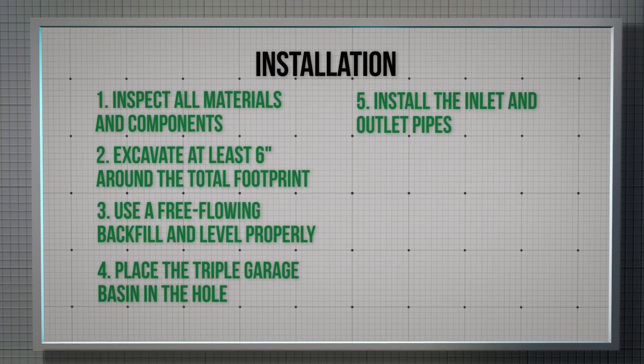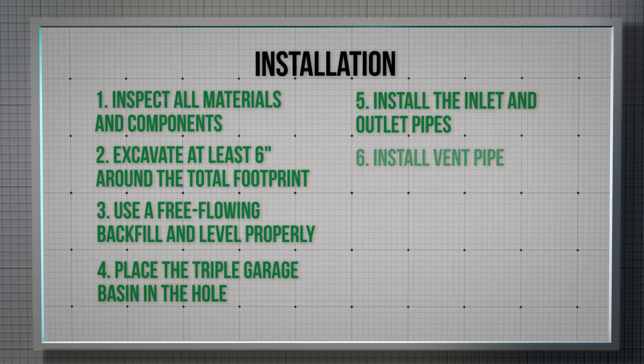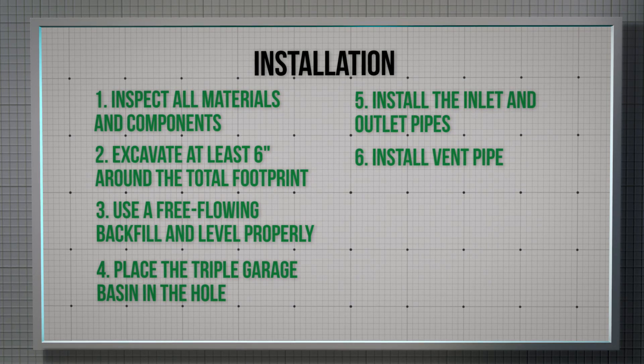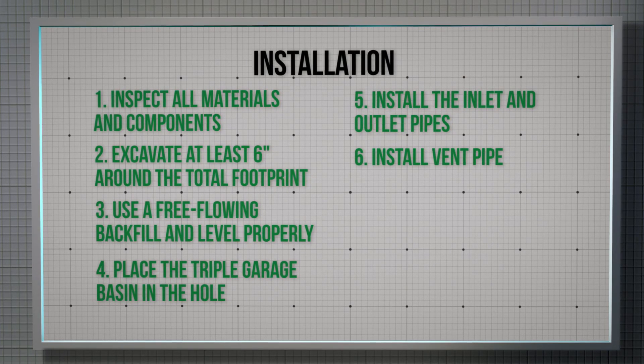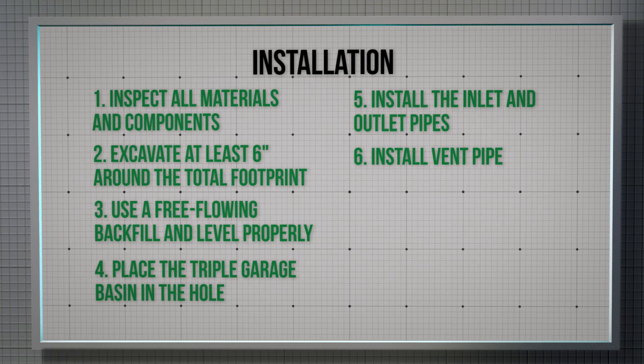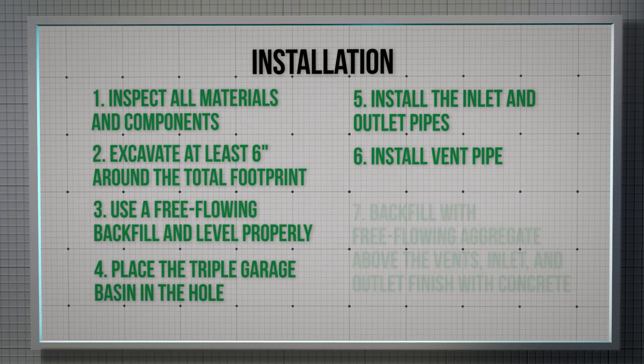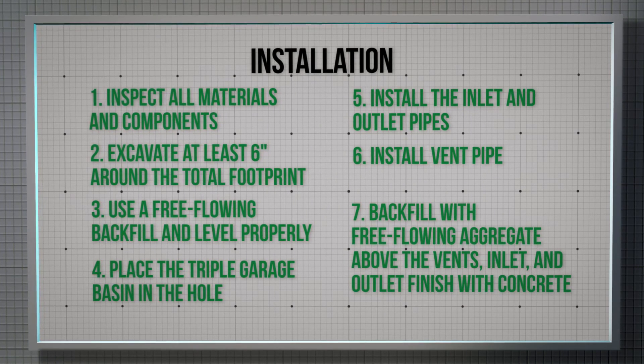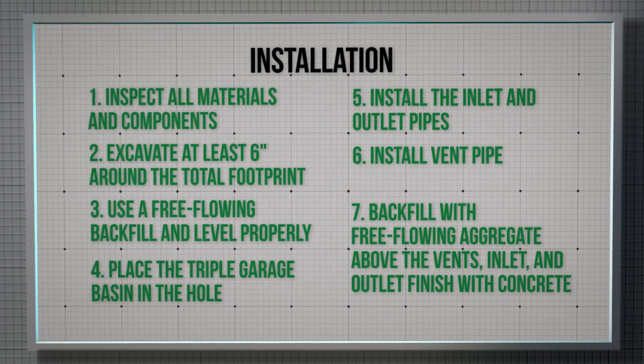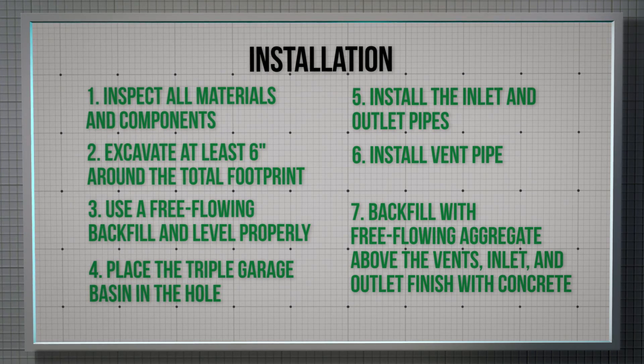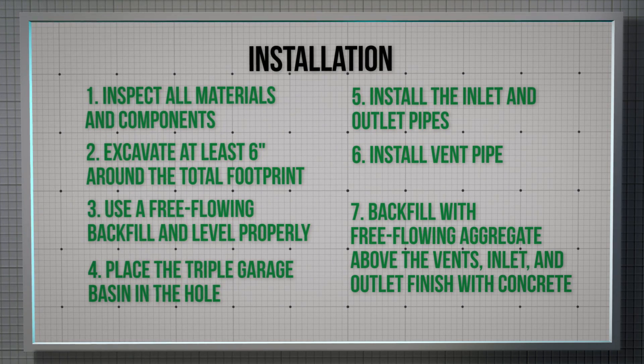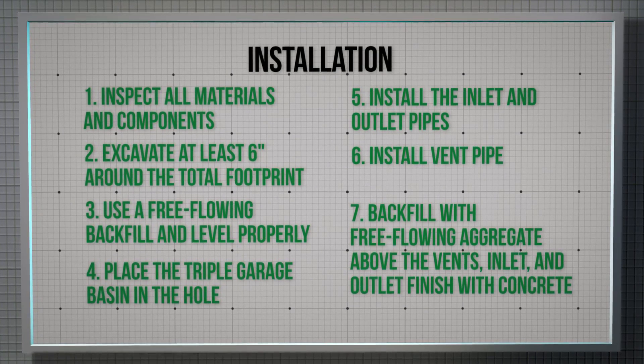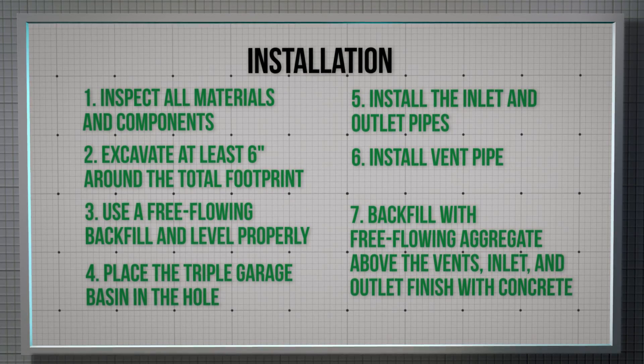Install the vent pipe into the three cast iron hubs for proper ventilation. Backfill with free-flowing aggregate above the vents, inlet, and outlet to protect the piping. Finish by pouring concrete to grade if applicable.